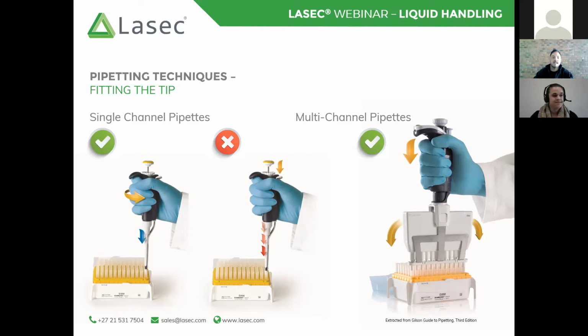In saying this, it's not always the case that we can have every single tip fitting every pipette perfectly. So it is a general recommendation that you do consider using the manufacturer's tip, because this basically assures you that it is going to fit the pipette and it is going to guarantee the best performance. And when it comes to fitting the tip, it also means that if you are using an appropriate tip, excessive force will not be required in order to fit the tip. So simply, for a positive displacement pipette, all you have to do is gently apply some downward pressure, ensuring obviously that that tip holder is lined up with the tip itself.